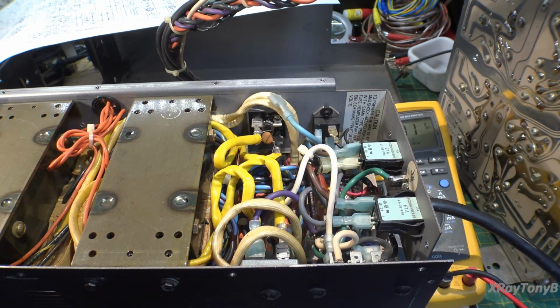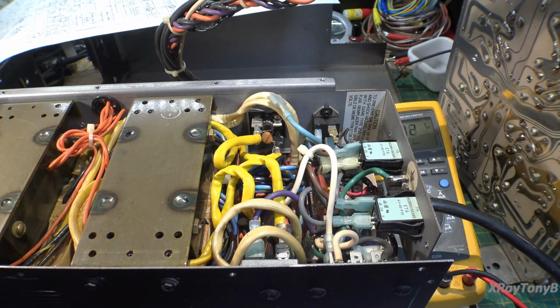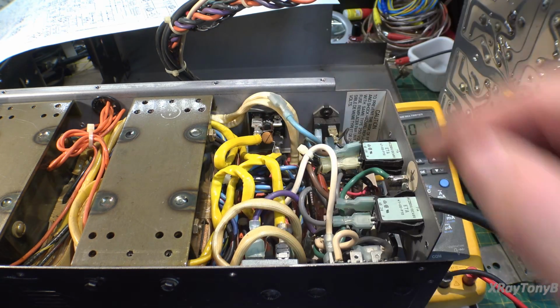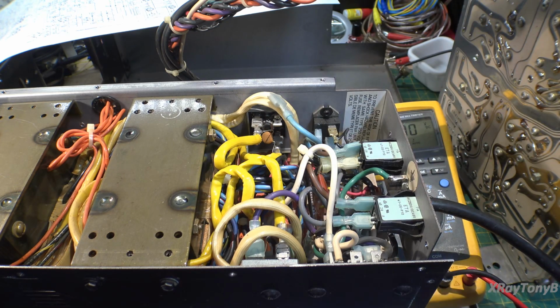Okay, to verify that the bridge rectifiers are not shorted themselves, we're just going to do a simple test. We're going to connect the inputs to them back up to the transformers, since we have our dim bulb, and we're going to just disconnect the outputs of them. Now, if the bridges are shorted, either one of them, the light's going to come on brightly.